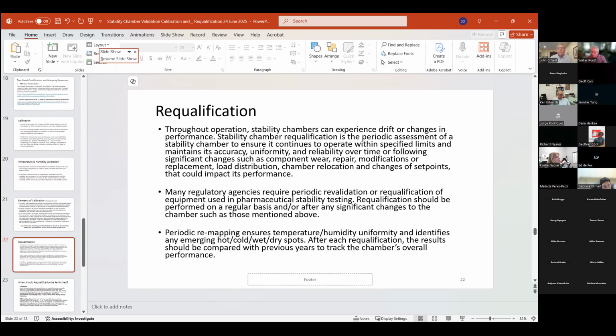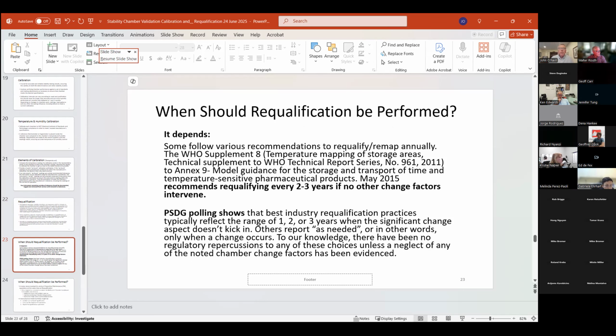You need to define when you're going to requalify. What do these things trigger? And some people just simply set it up on time intervals if nothing happens. We'll show you why in just a moment on the next slide. Many regulatory agencies require periodic revalidation or requalification of equipment used in pharmaceutical stability testing. Requal should be performed on a regular basis and or after any significant changes to the chamber, like we mentioned above. And then periodic remapping ensures temperature and humidity uniformity and identifies any emerging hot, cold, wet, dry spots, depending on whether or not you have humidity. After each requalification, the results should be compared with the previous years to track the chamber's overall performance. So trending becomes very important there.